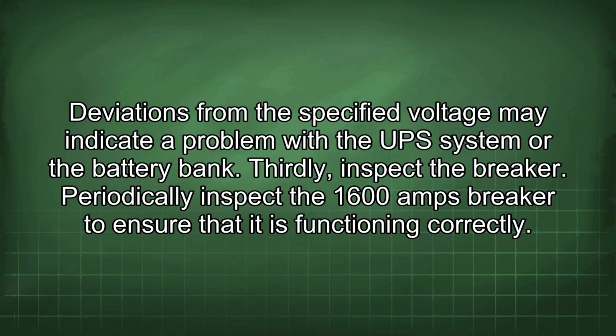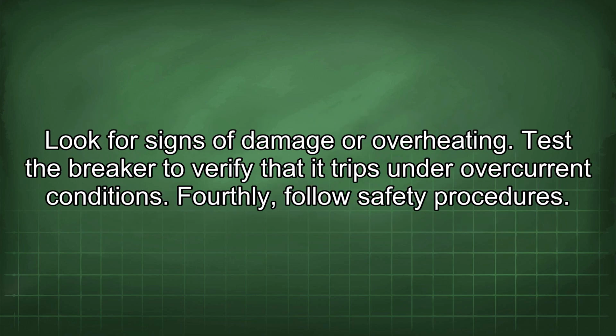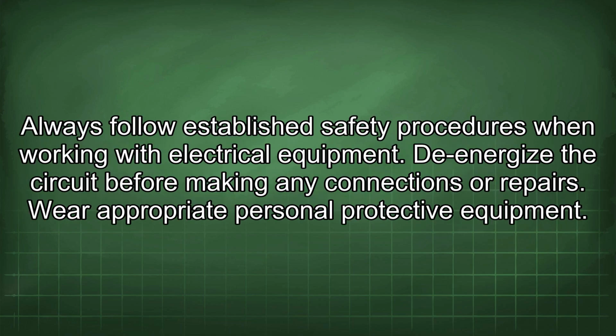Thirdly, inspect the breaker. Periodically inspect the 1600 amps breaker to ensure that it is functioning correctly. Look for signs of damage or overheating. Test the breaker to verify that it trips under overcurrent conditions. Fourthly, follow safety procedures. Always follow established safety procedures when working with electrical equipment. De-energize the circuit before making any connections or repairs. Wear appropriate personal protective equipment.